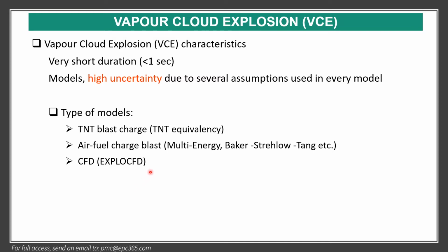But normally we don't use the TNT blast charge, in my experience in different oil and gas installations. Multi-energy, yes, but I highly recommend CFD, Xplo CFD, which is very easy to use, and you can import your plot plan and see the effect of congestion in the modelization of the explosion.